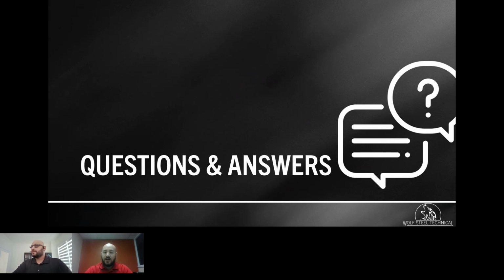Perfect. And then Luis had another question as well. He asked about the common components that fail the most within heat pump systems. So, can you answer that question? Yeah, a lot of the issues we've been finding are because of installer failure, based on where they install it and how far they install it from the unit. You have to follow the manufacturer specs. So if you are installing it above the vertical or the horizontal limits, you do have to install your oil traps. But for the most part, the heat pumps right now are pretty solid. When we come down to it, I've come across a couple of boards that usually go as well. It all depends on environmental factors as well.